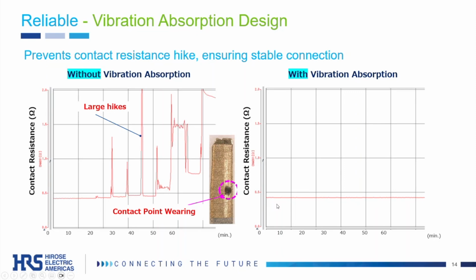The test compares samples with and without the vibration absorbing design, measuring contact resistance continuously during vibration. Without it, you can see large resistance hikes, and the photograph shows the contact point physically worn away. With it, resistance stays flat. That prevents contact point wearing that leads to resistance hikes and contact failure or temperature surge, which is fatal in safety critical applications.